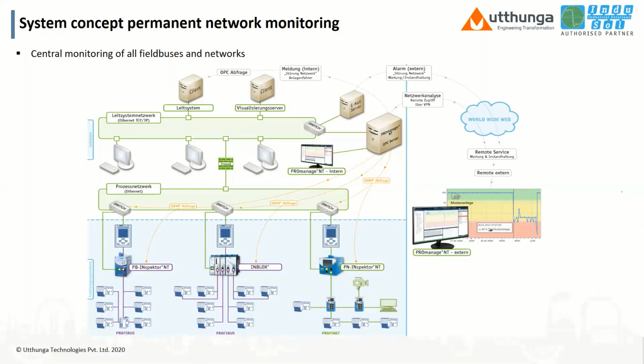So that is all about Profibus. Right now we are going to a little bit higher topic. This is the centralized monitoring solution. For example, if you have more than one network in the plant, which means more than one Profibus master system, here it is shown as 3 master systems. If you have 3 master systems, I will install 3 inspectors, because an inspector is dedicated to one master system. So I will install 3 inspectors, and I can connect them to a single dashboard using ProManage. That is our dedicated software for central monitoring. With that software, you can analyze the complete network, even if it is PROFINET, ASI, or CAN bus. Any network you can monitor in a single dashboard, and you can get the 24 hours data also.